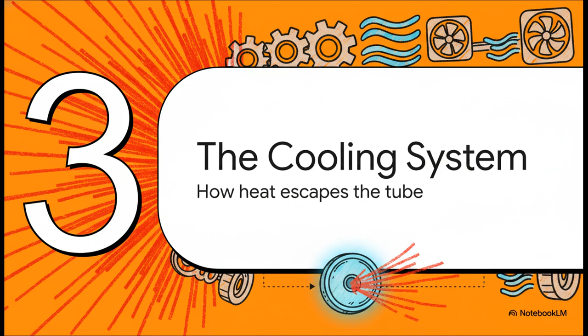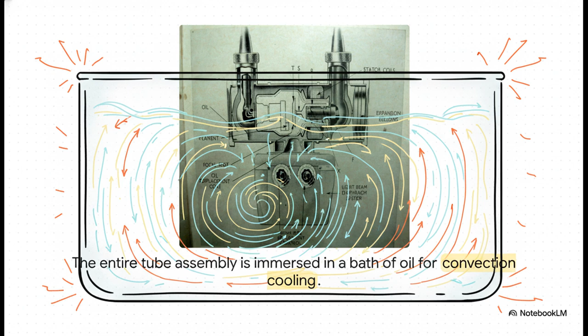This diagram shows us the next critical line of defense. The entire vacuum tube assembly is literally submerged in a special kind of oil. And this oil isn't just for lubrication or anything like that. Its main job is to pull heat away from the glass through a process called convection. So the heat actually goes on a 4-step journey to escape. First, conduction pulls the heat from that tiny focal track into the main body of the anode disk. Second, the glowing hot anode radiates that heat across the vacuum. Third, convection carries the heat from the tube through the oil to the outer housing. And finally, that housing gets rid of the heat, dissipating it into the room, usually with some help from cooling fans. It's like a beautifully choreographed relay race for thermal energy.